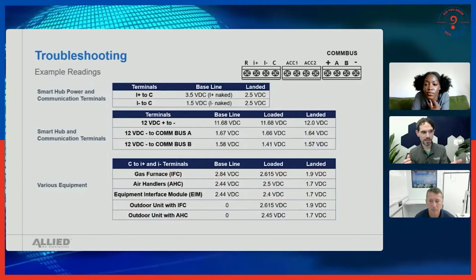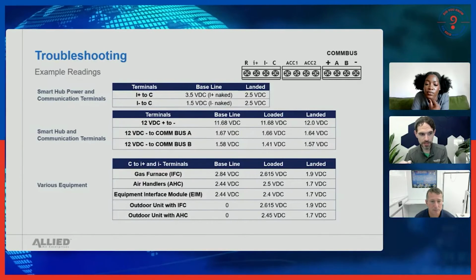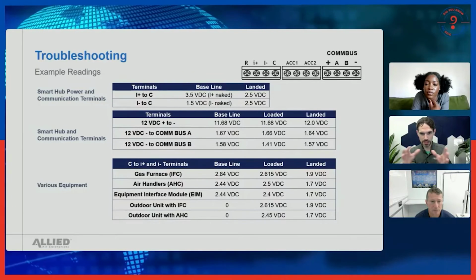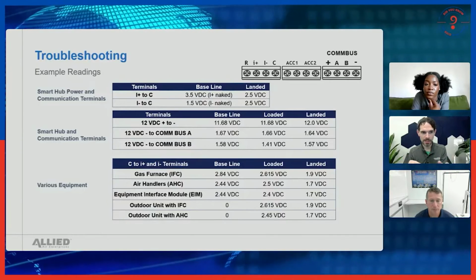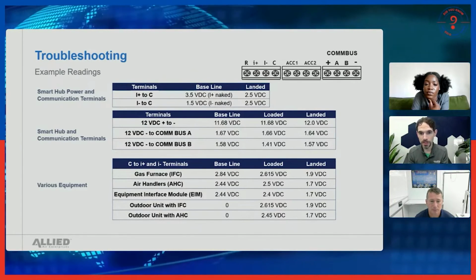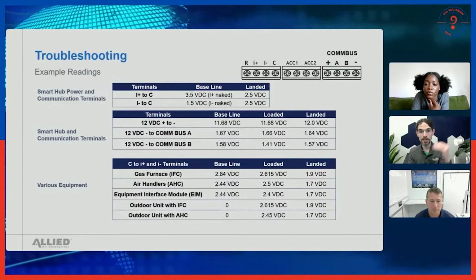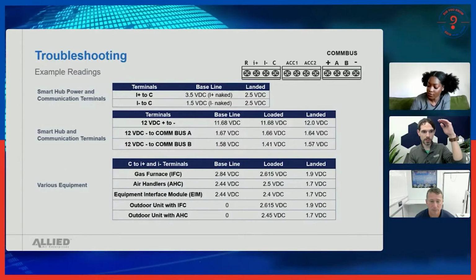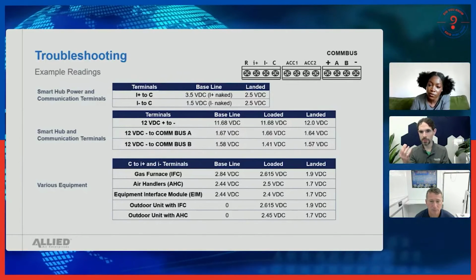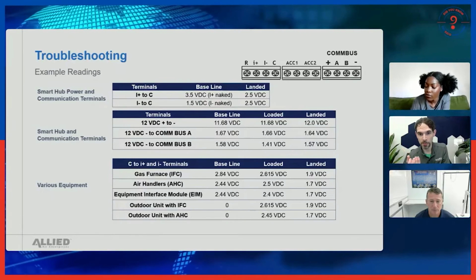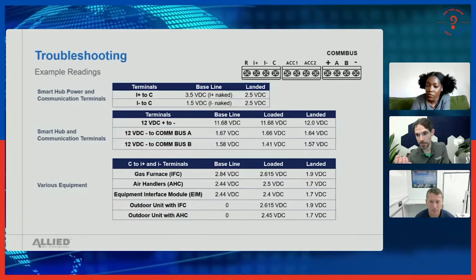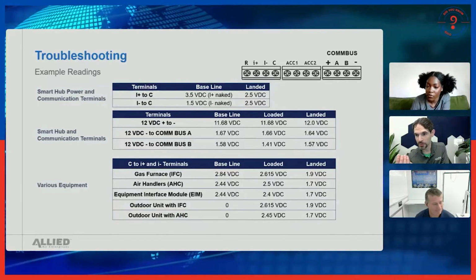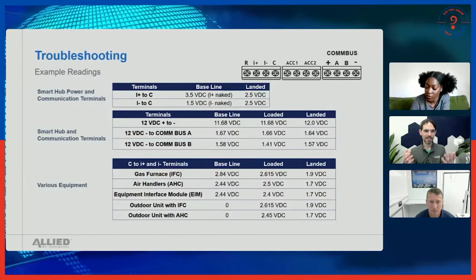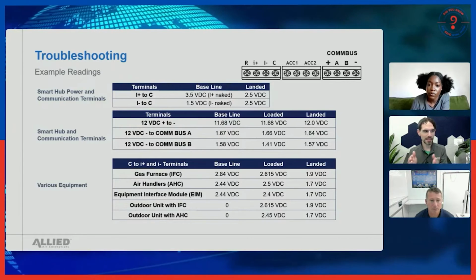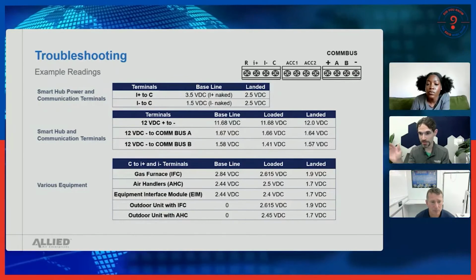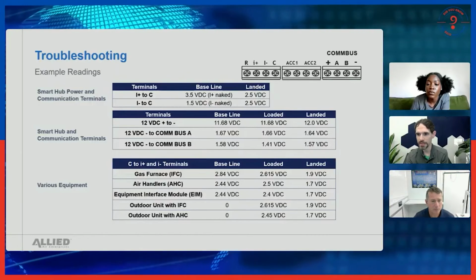If you look at the baseline side, a lot of times there's a very low voltage that we would read in a connected system, and then even your 12 volts—is it bumping it down correctly from your higher voltage to a 12 volt section? We talk about how good your reading is off your transformer. If somebody says I'm reading 24 volts exactly, that might be the problem, because when do you ever see exactly 24 volts? That's a very common thing. So these are just examples, just a general point to talk to.